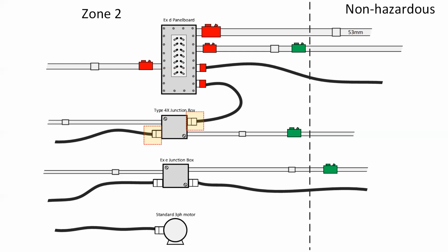There is nothing within 18-154 that indicates I would need to have an explosion seal or an FFM seal. And due to that, we are open to simply placing a standard TECK cable connector with no sealable fitting.